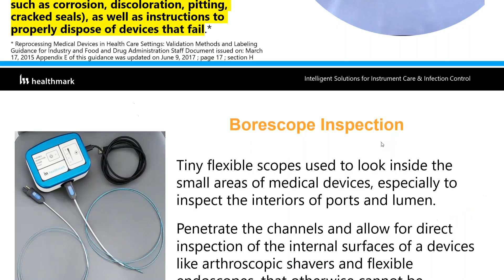But for inspection after use, FDA recommends that all routine cleaning instructions should include instructions for visual inspection, which may include the use of magnification. So FDA basically recommends that you must have some lighted magnification on hand to check instruments that are in use. It's also important that visual inspection instructions include what is acceptable. For example, if you see something like this, is it acceptable? And then you need to make that determination to put it back in use or not.